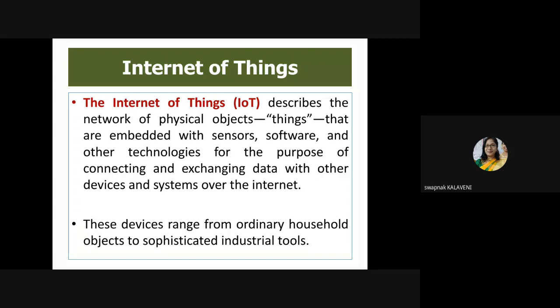Based on the information, the action will be taken by the artificial intelligence network or whatever algorithm we have. Say, for example, if the transformer is overloaded, we have to remove the loads, or we have to keep the transformer within the level, meaning certain loads have to be switched off. For that purpose, the loads have to be sensed. The sensors which are fixed on the transformer continuously monitor the load on the system. Based on the data supplied to the central control room, the observer arranging the data will come to the conclusion that the load is going beyond the permissible limit. Some action has to be taken, and the artificial intelligence network will take care of what action to take. So data, information inside. This is nothing but the IoT.